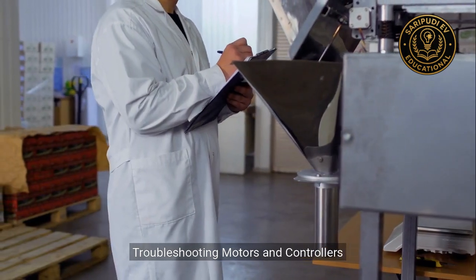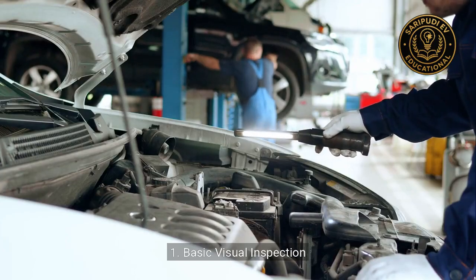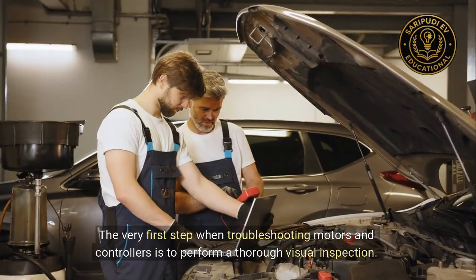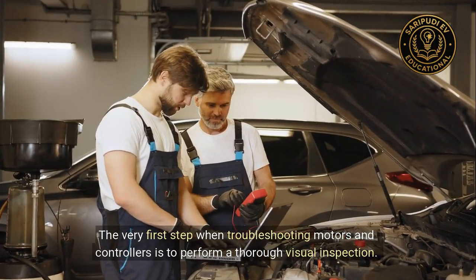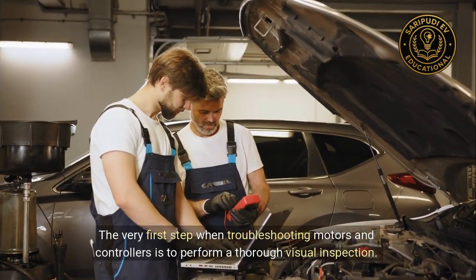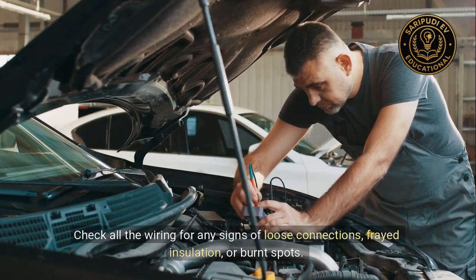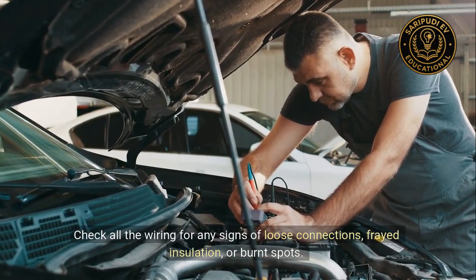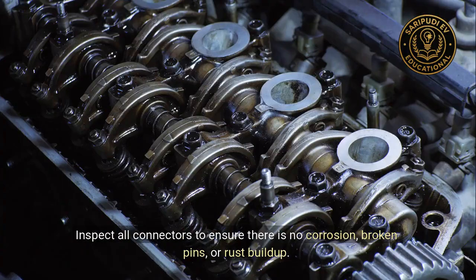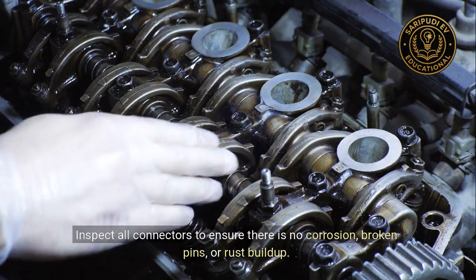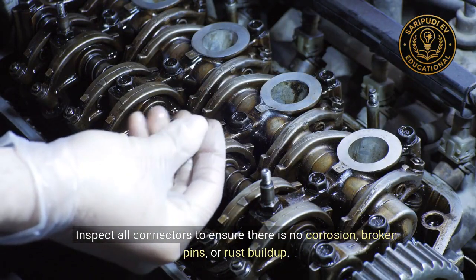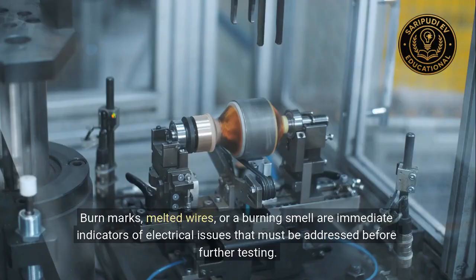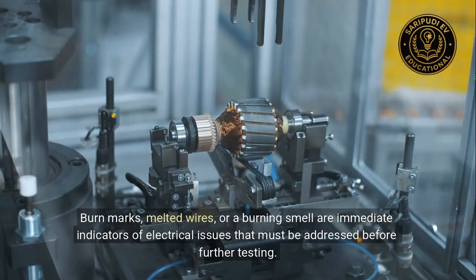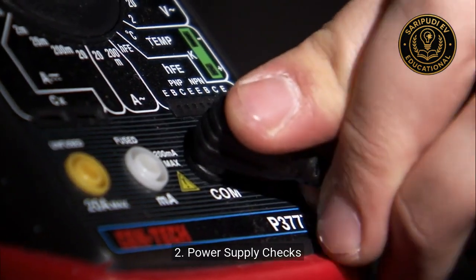Troubleshooting motors and controllers. 1. Basic visual inspection. The very first step when troubleshooting motors and controllers is to perform a thorough visual inspection. Check all the wiring for any signs of loose connections, frayed insulation, or burnt spots. Inspect all connectors to ensure there is no corrosion, broken pins, or rust buildup. Burn marks, melted wires, or a burning smell are immediate indicators of electrical issues that must be addressed before further testing.